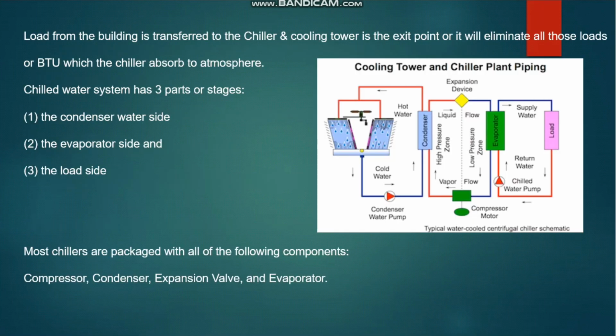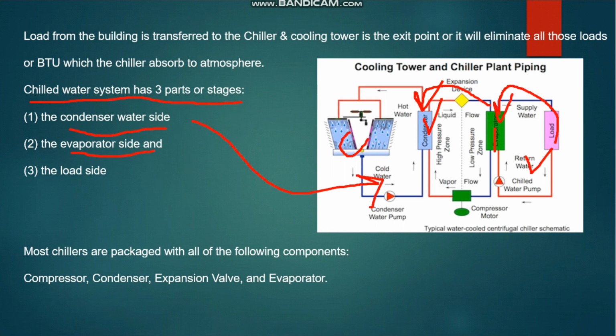Here, as I explained, the building load will be transferred to the chiller in the evaporator, and at the condenser the load from the chiller will be transferred to the cooling tower. So the chilled water system has three parts or stages. That is the condenser water side, which is the open loop side, the evaporator side, which means the chiller side, and also the load side, which is the building load side. Coming to the chiller, there are four important things as I explained: compressor, condenser, expansion device and evaporator.